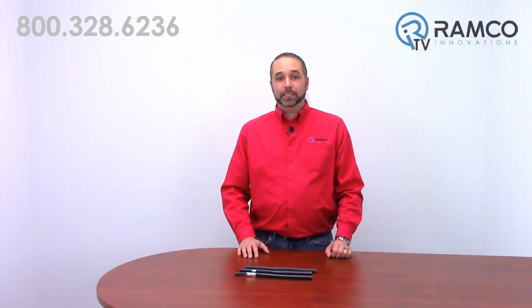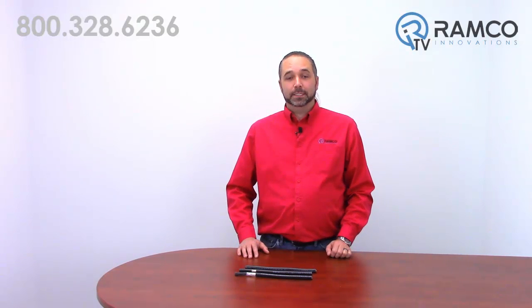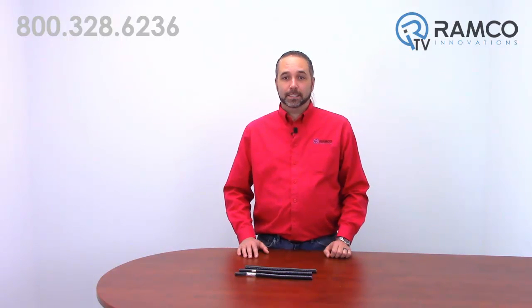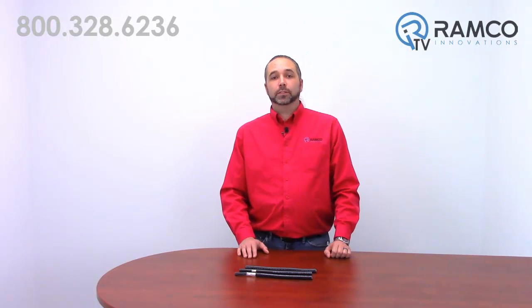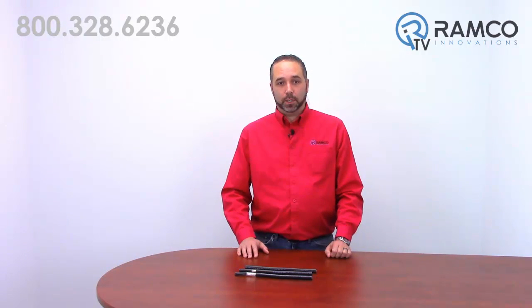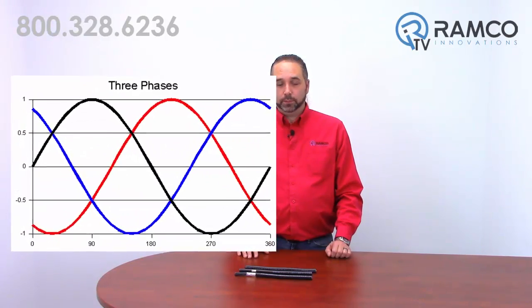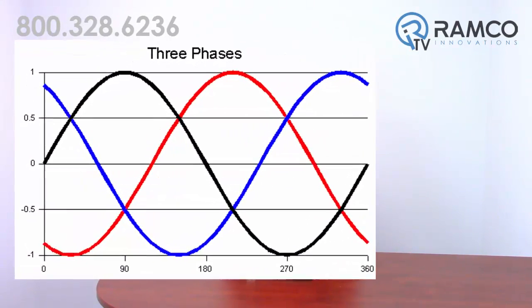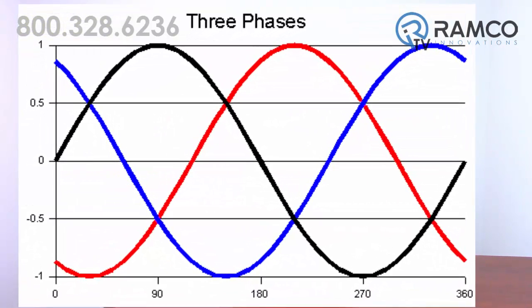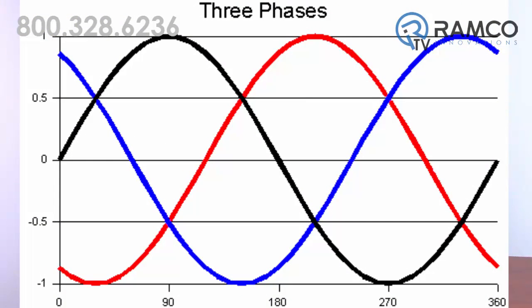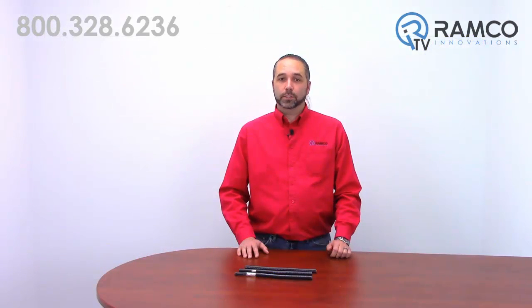All current IGBT based drives produce a chopped DC wave that simulates an AC sine wave to a motor. This chopped DC signal can cause some problems. Common mode current is created by common mode voltage, which is the sum of all three phases to ground. In a standard balanced three-phase AC system, the sum of all three phases is equal to 0. But with this chopped DC output, this is not the case.